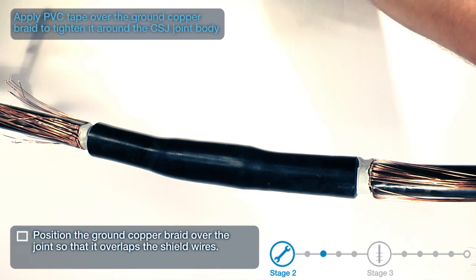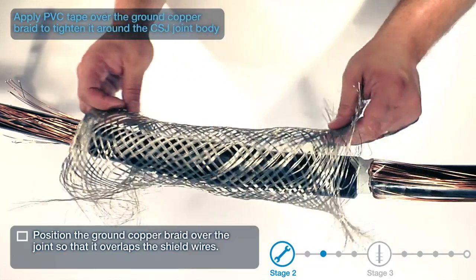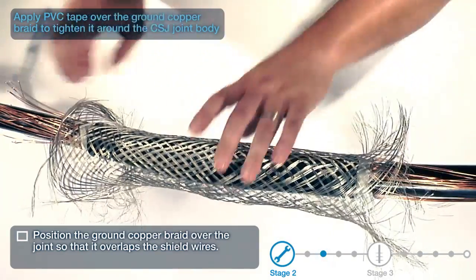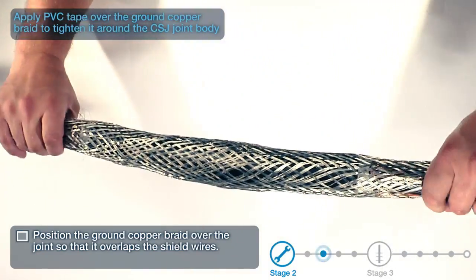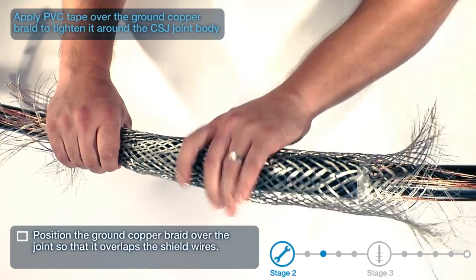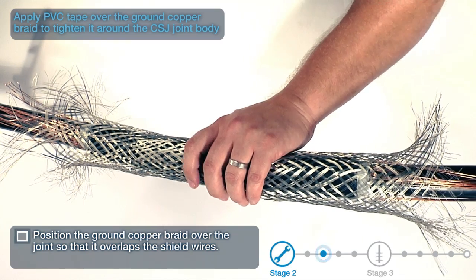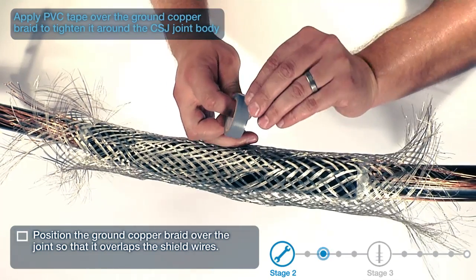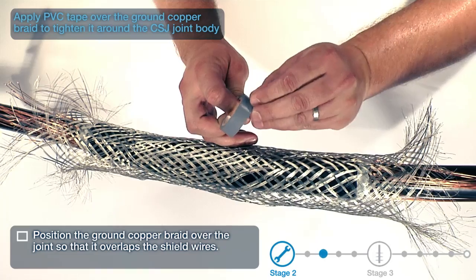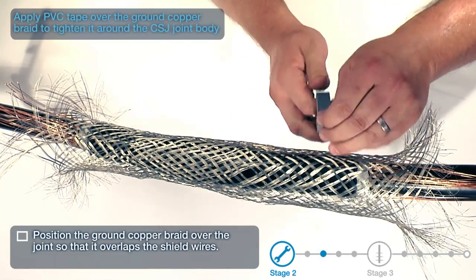Position the ground copper braid over the joint so that it overlaps the shield wires. Apply PVC tape over the ground copper braid to tighten it around the CSJ joint body.